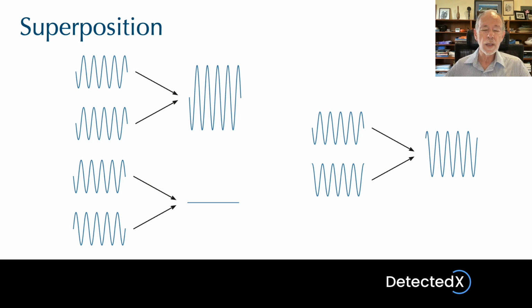So the main thing is what I'm showing on the top left, that we want contributions to the ultrasound from different points on the face of the transducer to all arrive at the focal point at the same time, because this will maximize the intensity at that focal point.